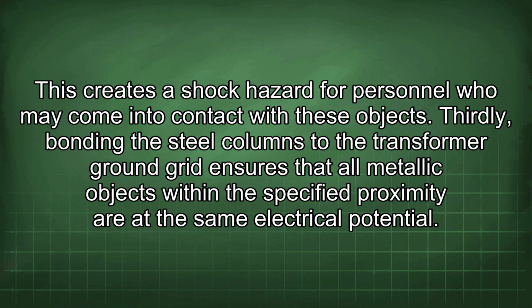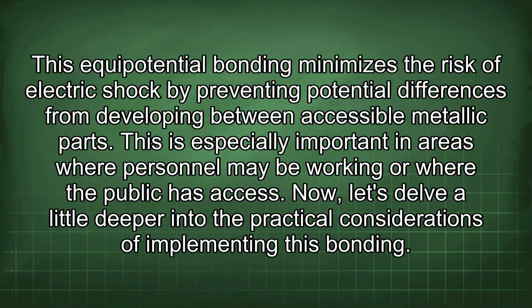Thirdly, bonding the steel columns to the transformer ground grid ensures that all metallic objects within the specified proximity are at the same electrical potential. This equipotential bonding minimizes the risk of electric shock by preventing potential differences from developing between accessible metallic parts. This is especially important in areas where personnel may be working or where the public has access. Now, let's delve a little deeper into the practical considerations of implementing this bonding.